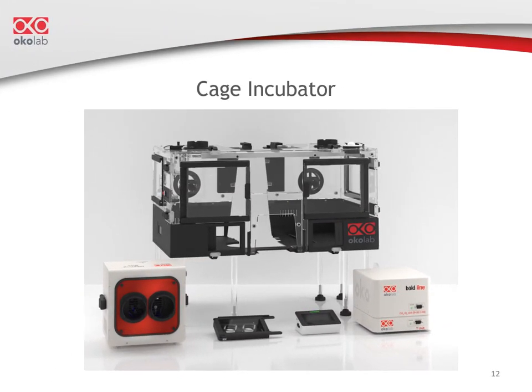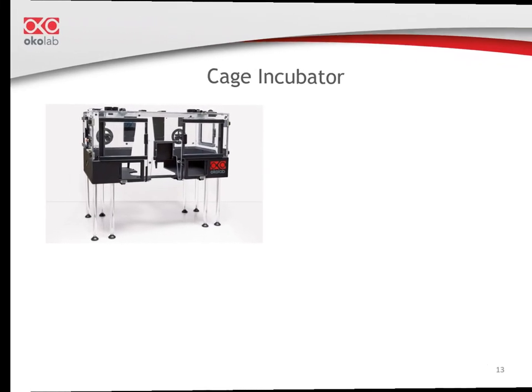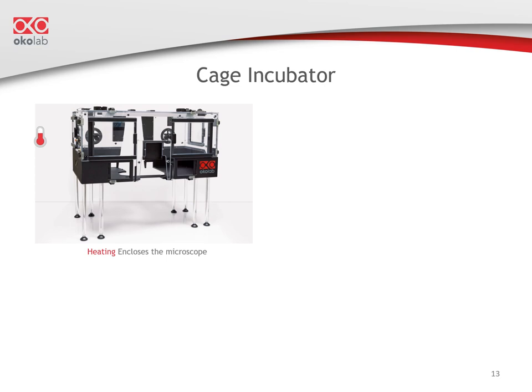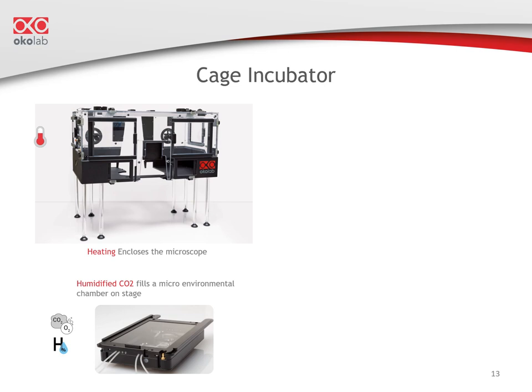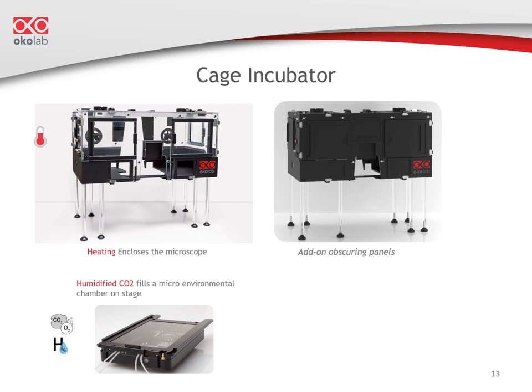Let's talk about cage incubation systems. Remember, in this case, heating encloses the microscope and the objective and nose piece are inside the enclosure at 37 degrees. The microenvironmental chamber containing the sample, located on the stage, prevents humidified CO2 from dissipating. We offer transparent enclosures — if needed later, you can add obscuring panels, select a black enclosure from the start, or even a black laser-safe one.